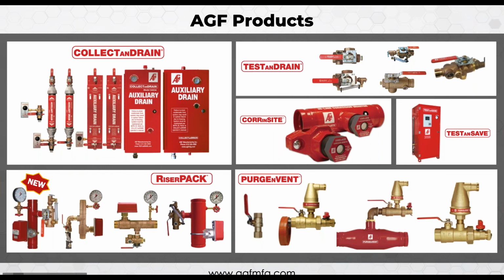Very rarely do we see spot corrosion on a specific floor of a building, unless it's a trapped air situation. When we see corrosion-related damage, it's typically widespread throughout a building, and again, it's due to either the condition of the water or the overall condition of the pipe. So having a few of these located around the building gives us the best indication of the quality of the system and the quality of the water.